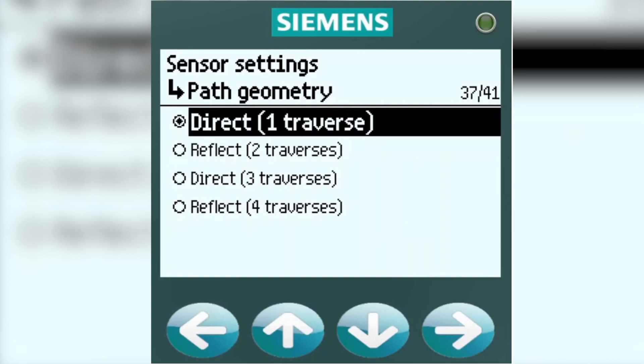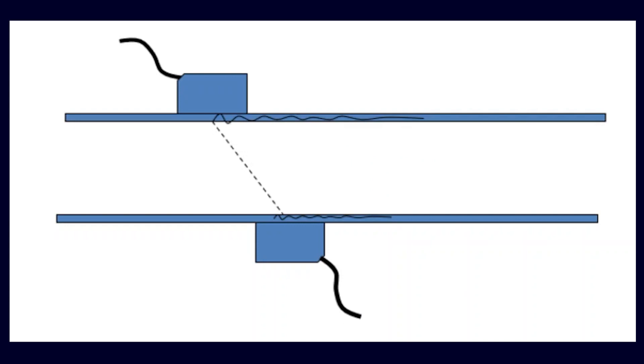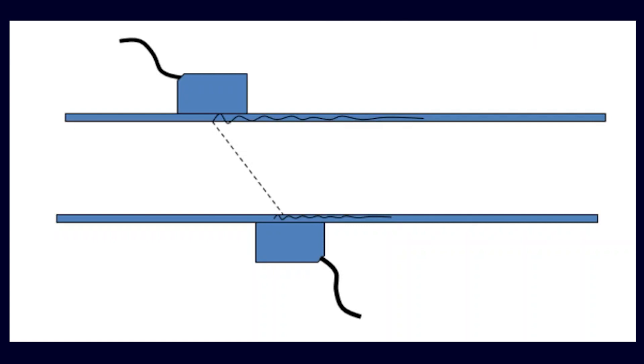Direct 1-Traverse. This is one pass through the pipe, or one traverse. One sensor is on one side of the pipe, the other is on the opposite side. What you're looking at here is a top view. This is typically used when there's not enough space to mount in Reflect, or if you're using non-metallic pipe. You're also probably best off using this when you have ductile iron pipes.